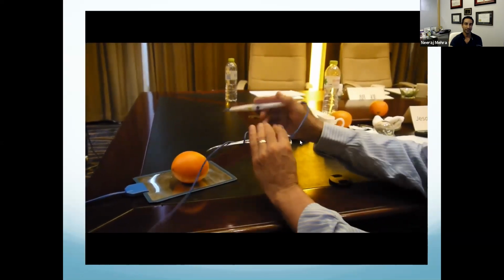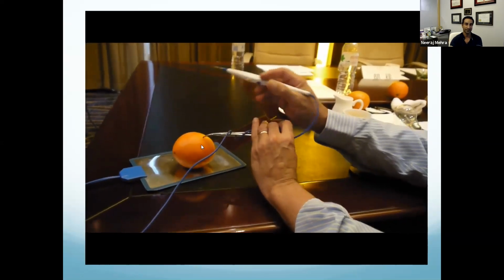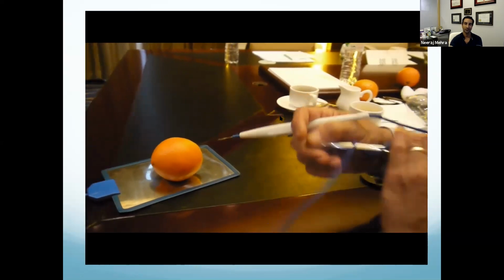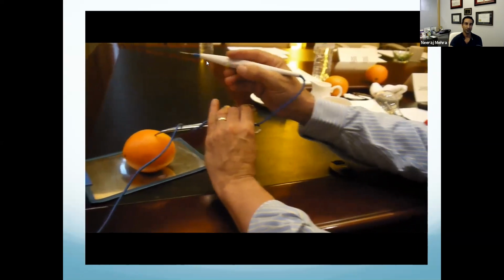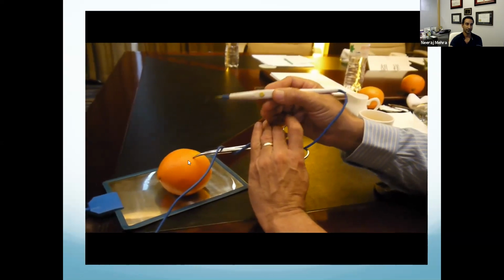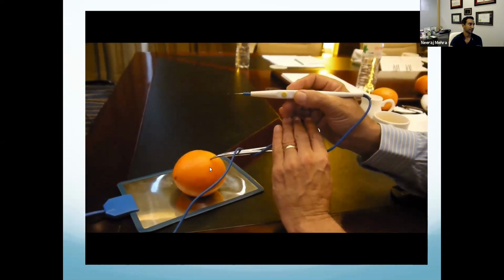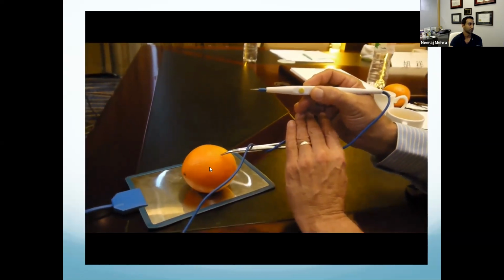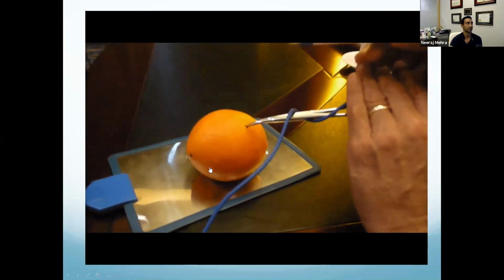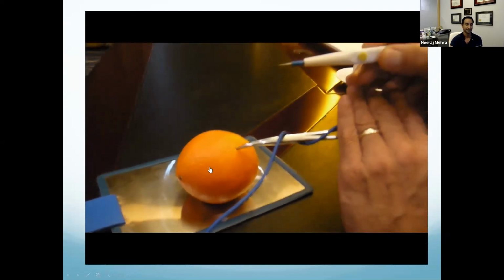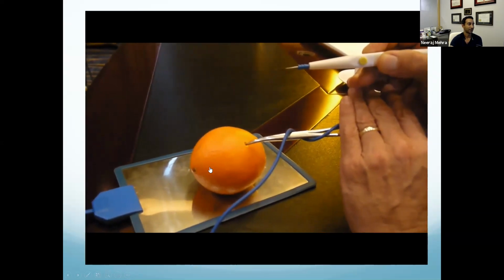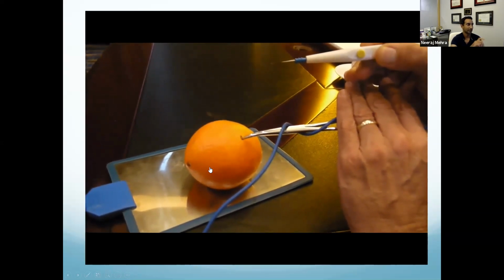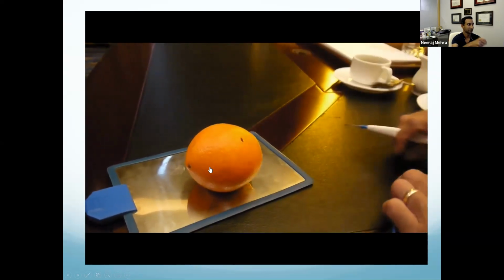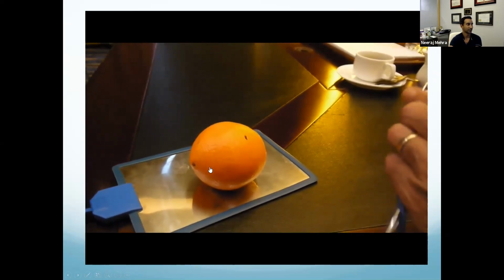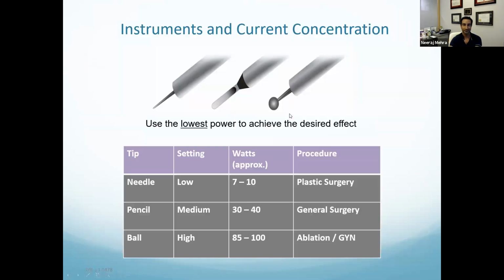If there's a way where this is an area of less resistance than where your electrode is going, then it's going to go there, creating an electrical current, and you're going to have a little burn and a fire right over the drapes. That's why they say don't wrap your instrument in a snap — that's why there are plastic holders, holsters for your electrode. That's why you use that and not the snap.